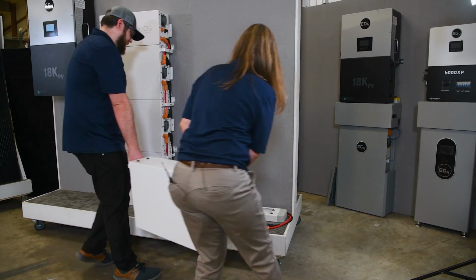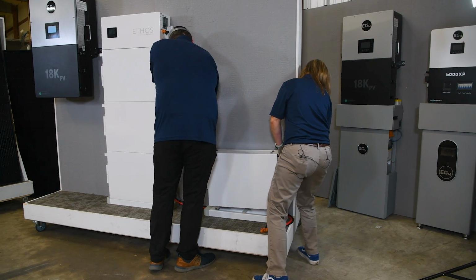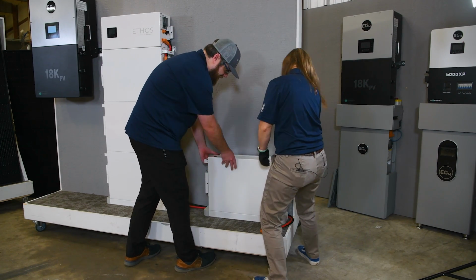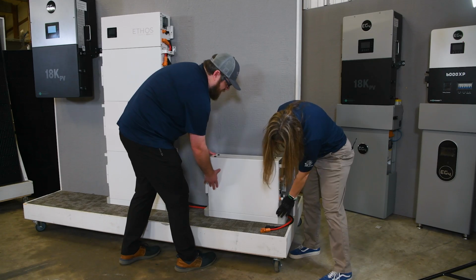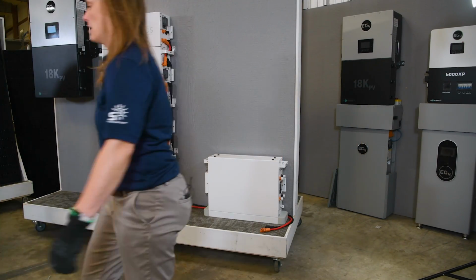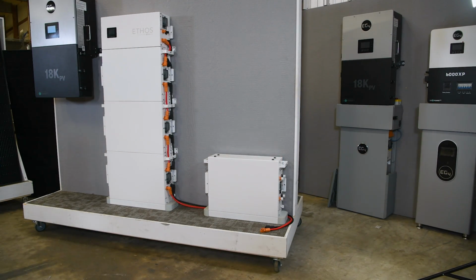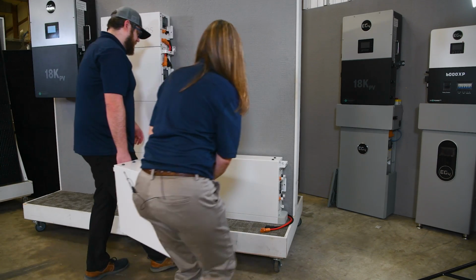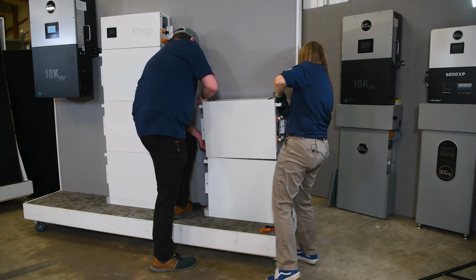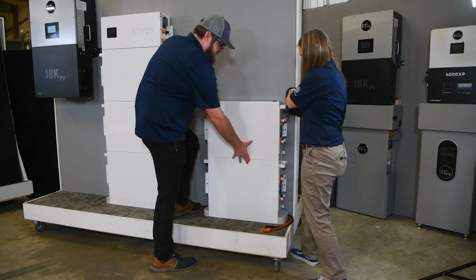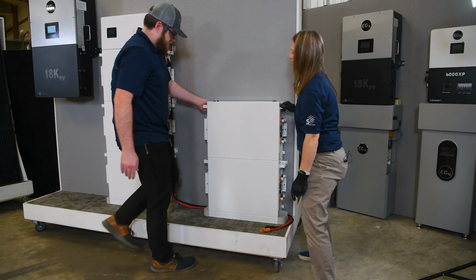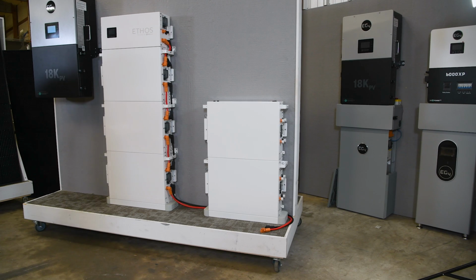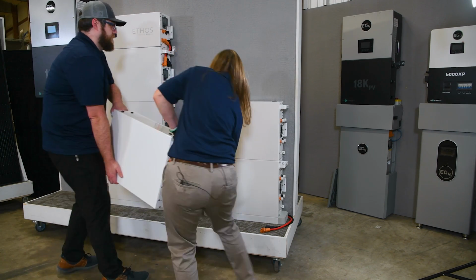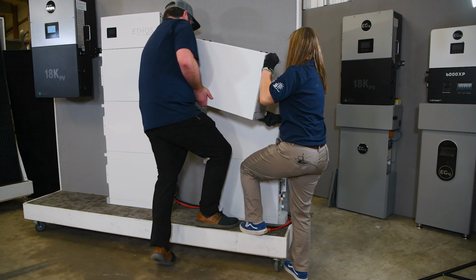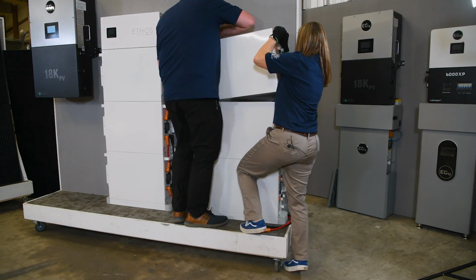BigBattery recommends maintaining a 12-inch gap between each ETHOS battery stack, as well as a 12-inch distance between the controller box and the inverter. This recommendation serves dual purposes. First, it ensures optimal airflow and heat dissipation among your batteries, essential for maintaining their efficiency and longevity. Secondly, the communication and battery cables are designed with this specific spacing in mind. Setting them too far apart might mean the cables won't reach, while placing them too closely could compromise airflow, causing the batteries to overheat and reducing their operational efficiency and overall health.